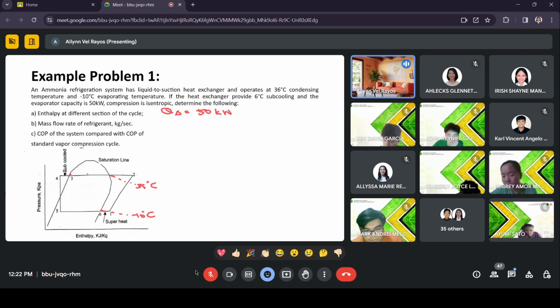Subcooled: this point is 36 degrees Celsius since it's equal to the condensing temperature, but the temperature at point 2 is different. So in this case, we have temperature 4, our subcooled temperature. We take our 36 degrees Celsius and subtract 6 degrees Celsius since we subcooled, meaning temperature 4 is 6 less than 36, so 30 degrees Celsius.